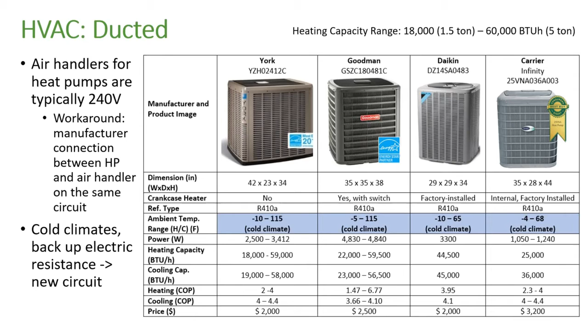And one important consideration I've learned throughout this process of writing this book is that air handlers for heat pumps are typically 240 volt, whereas if you have a typical furnace and air conditioning system, the air handler for your furnace is 120 volt. So in thinking about the ducted systems, some manufacturers have a workaround for this. They'll have a way to connect the compressor or heat pump circuit to the air handler. And that was the major lesson learned for me on the ducted heat pumps here.